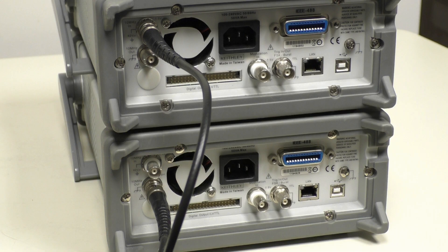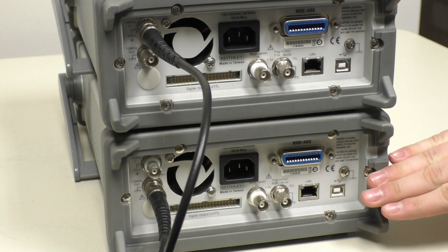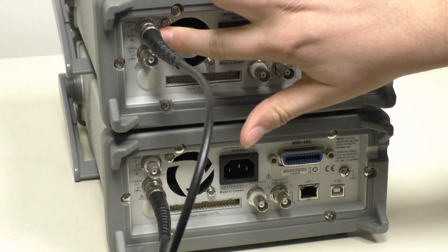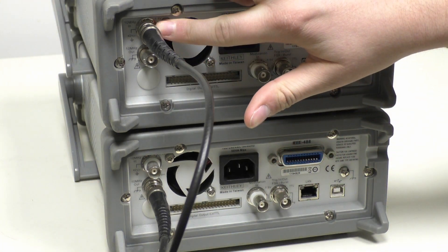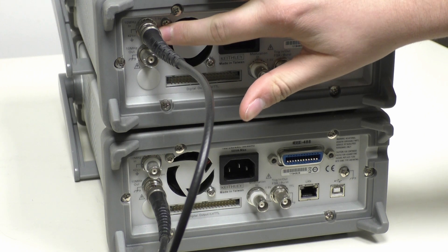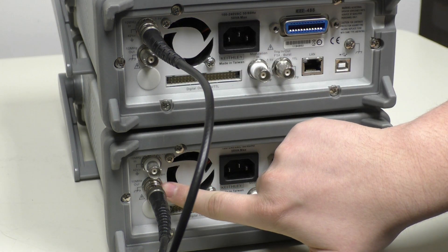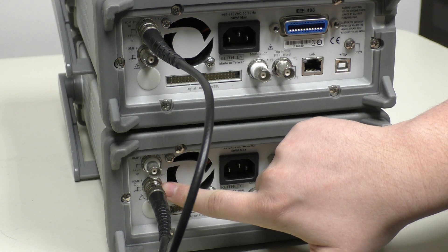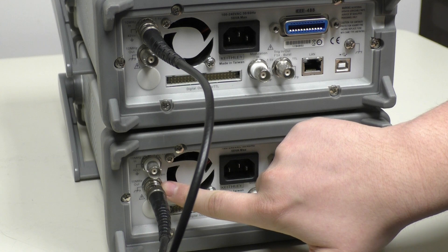First, you'll need to connect the two 3390s with a coax cable. You'll connect the top connector on the first instrument, which is the 10 MHz in, to the bottom connector on the second instrument, which is the 10 MHz out.